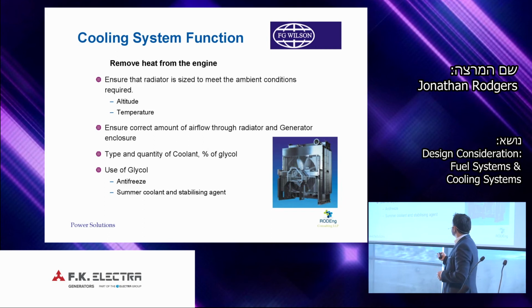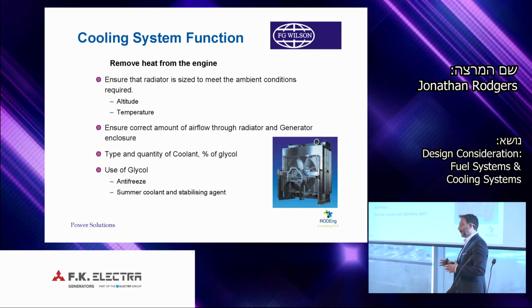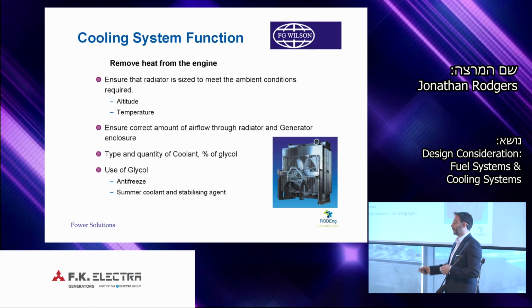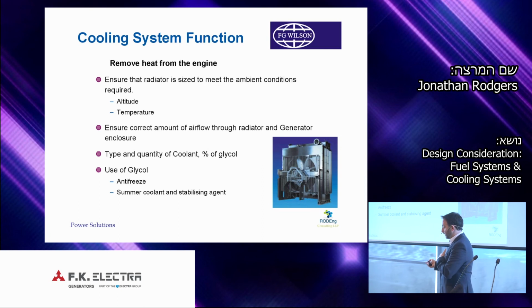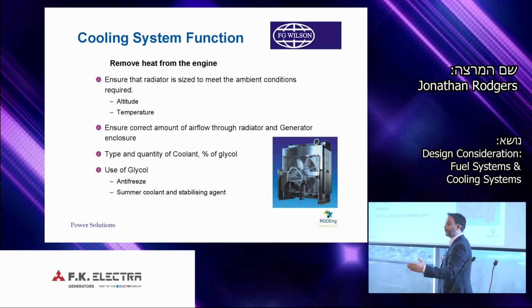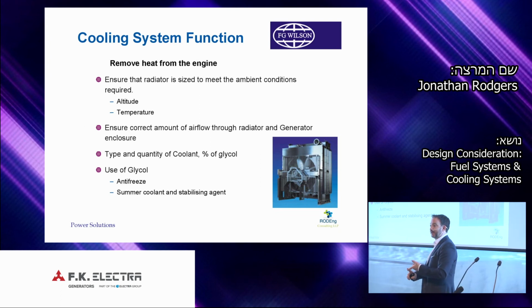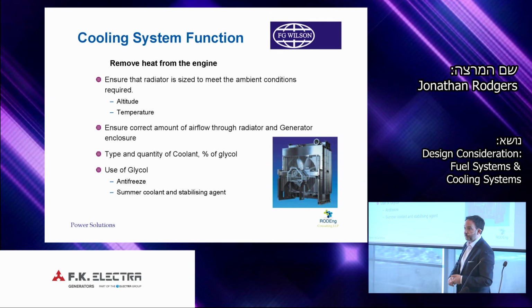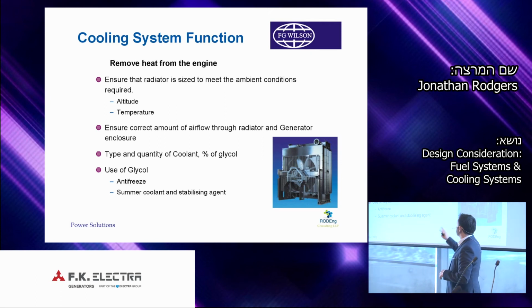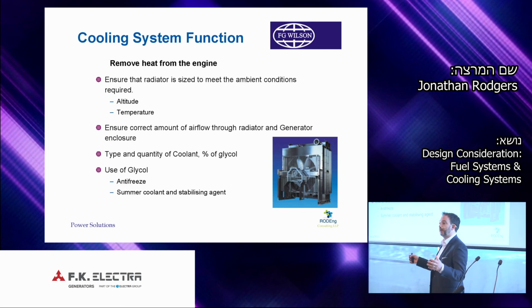So when we have our sizing of our cooling group, we then have an airflow requirement, and that airflow needs to be capable of going through the radiator and the restriction of the radiator, but also anything in the enclosure or plant room. So that's our attenuators, our louvers, our ductwork. All of that means we need to have our pressure drop capability for the airflow to allow it to be packaged.